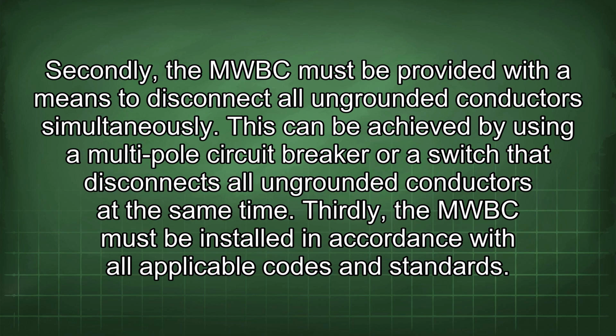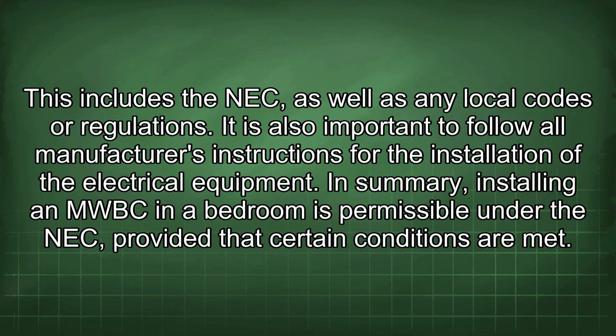This can be achieved by using a multi-pole circuit breaker or a switch that disconnects all ungrounded conductors at the same time. Thirdly, the MWBC must be installed in accordance with all applicable codes and standards. This includes the NEC, as well as any local codes or regulations. It is also important to follow all manufacturers' instructions for the installation of the electrical equipment.